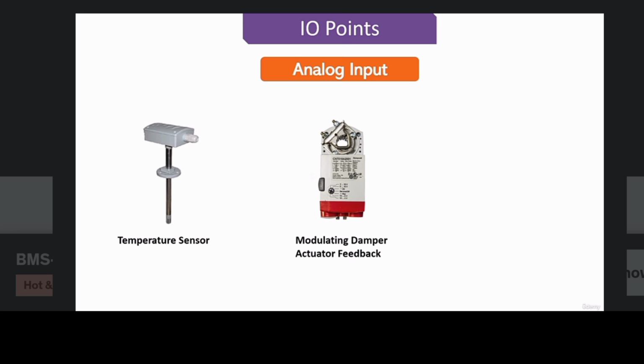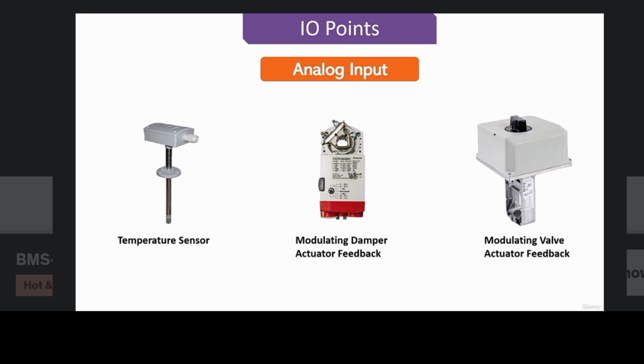This feedback value can be 0 to 10 volt DC. So if the actuator is fully closed, it will give 0 value to the DDC controller, and if it is fully open, it will give 10 volt DC to the DDC controller. And if it is half open, it will give a 50% value to the DDC controller. Similarly, the valve actuator feedback is also an example of analog input.